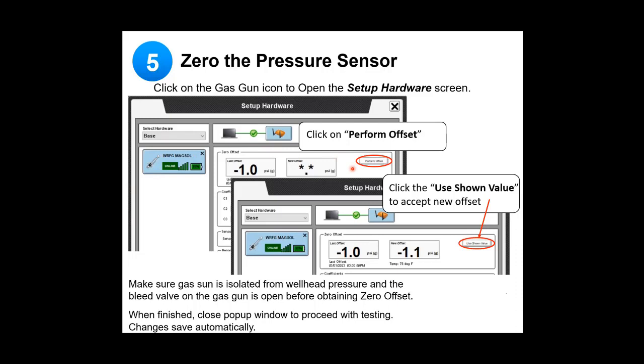As I was speaking of earlier, we want to make sure that we obtain the zero offset with no pressure on the sensor. In our case, using the wireless remote fire gas gun, we're going to make sure that the valve is closed to the wellhead, the gun is attached to the wellhead, and we're going to open the valve on the side of the gun, which is called the bleed valve, ensuring that that pressure transducer is subjected to zero pressure or atmospheric pressure prior to getting the offset. We're going to select Perform Offset. Once the offset stabilizes, we're going to lock in that value by using Shown Value.